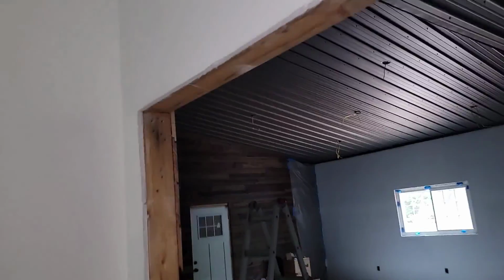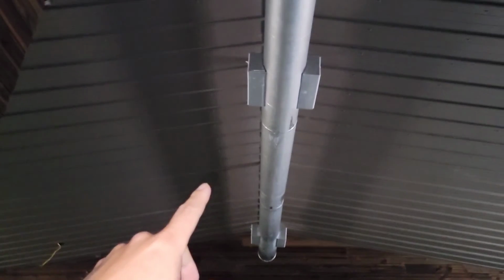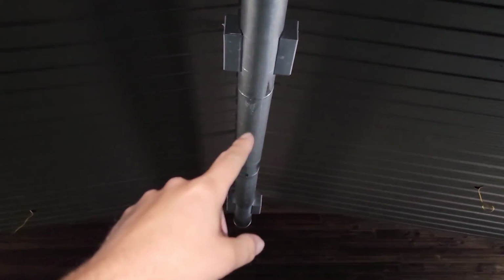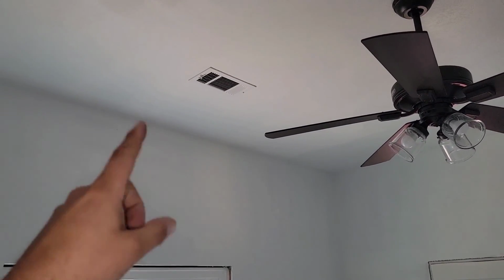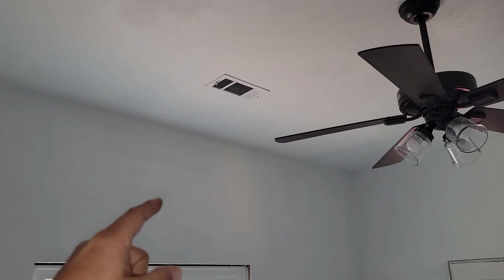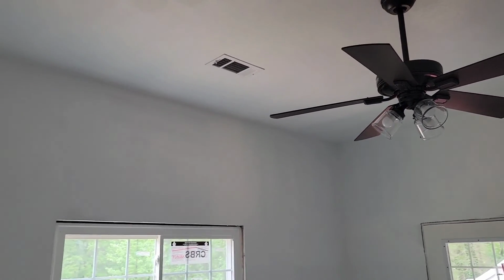I'm going to go over the vents real quick and count the CFM. So one 8-inch line, 200 CFM. 2 more 6s, 3 400. Another 6, that's 500. That's 500 CFM so far. And then we got, this would be equivalent to 6-inch lines, 4x12 register. So that's 400 more. So 1, 2, 3, 4. So far we got 200, 300, 400, 500, 600, 700, 800, 900. And then another 6, that's 1,000 CFM. We should have one more, and this is an 8-inch line, 6x12. So that's 1,100, 1,200. So 1,000 plus 200 more CFM, 1,200 CFM total.